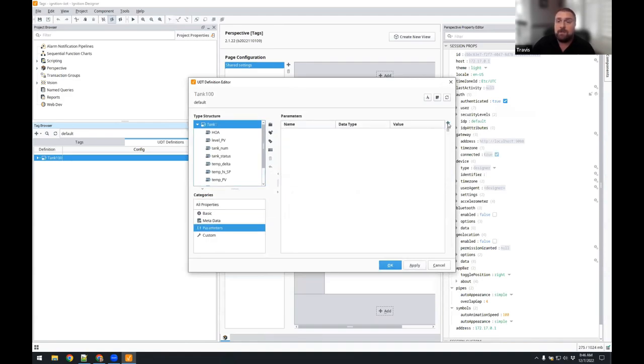The first thing we do is we give it parameters. Now, I was saying before how these models have parameters. So I'm going to create one that's called asset ID, maybe an asset serial number. Maybe you want to have a location. Where is that thing located? And these are all going to be strings here. And I'm going to have which OPC server do I want to grab this data from? And last but not least, a prefix for where I want to point to the tags in the PLC.